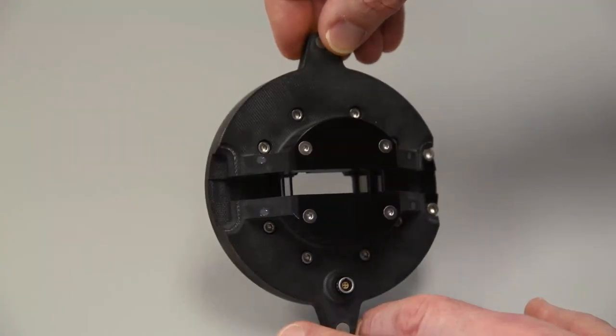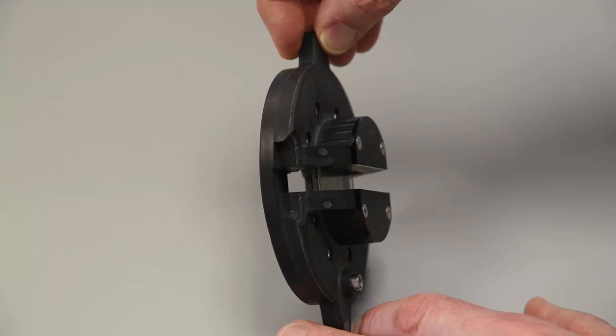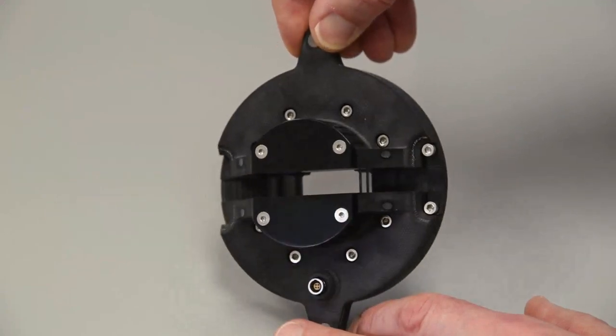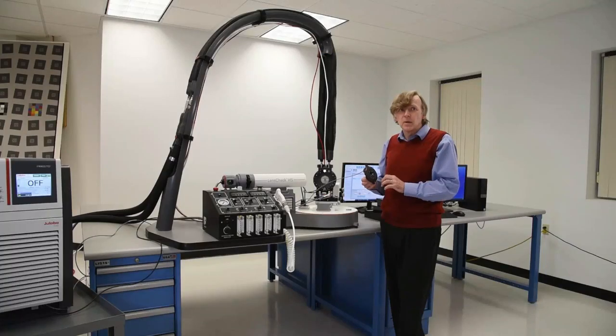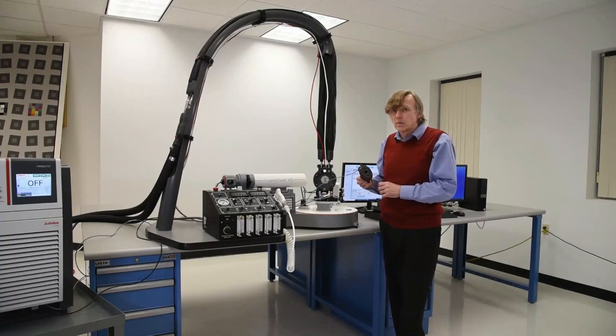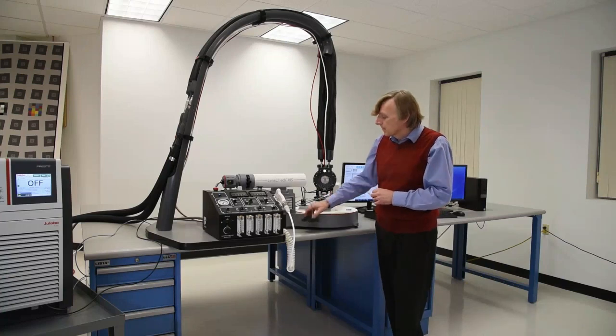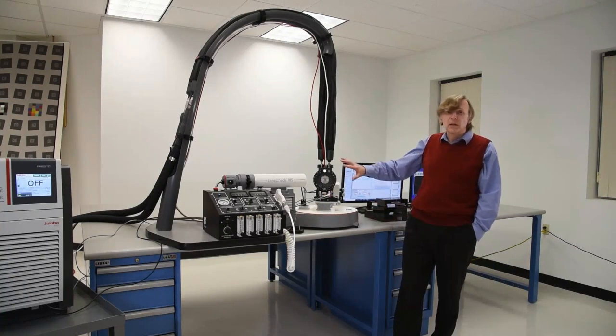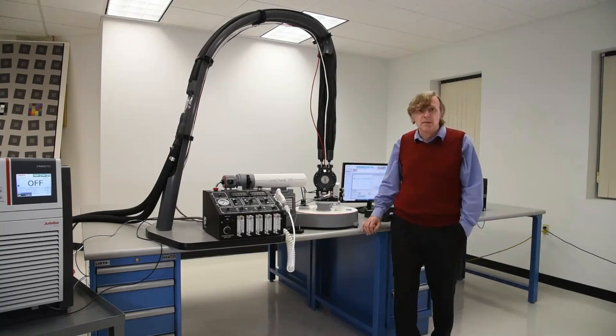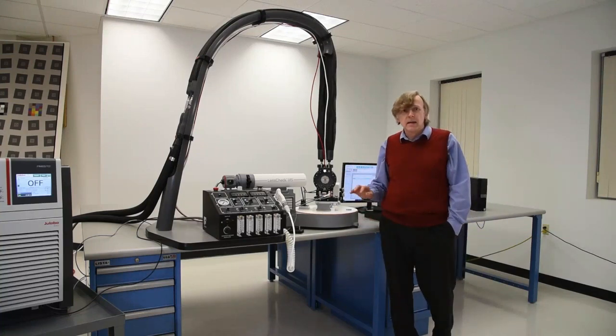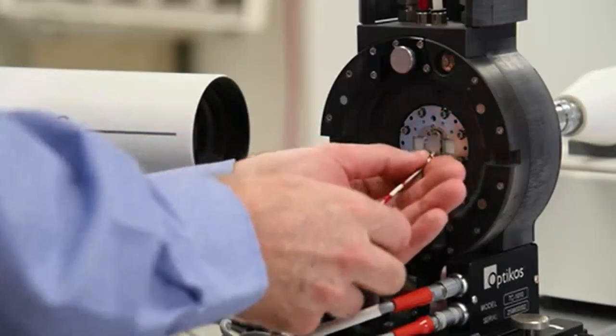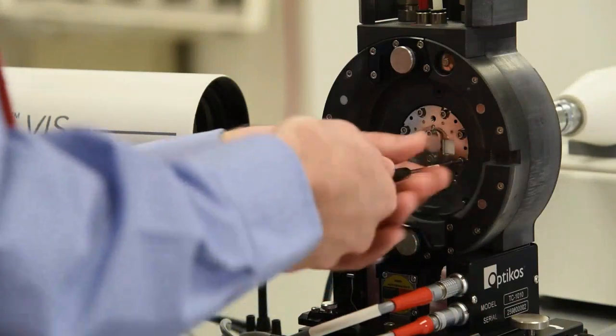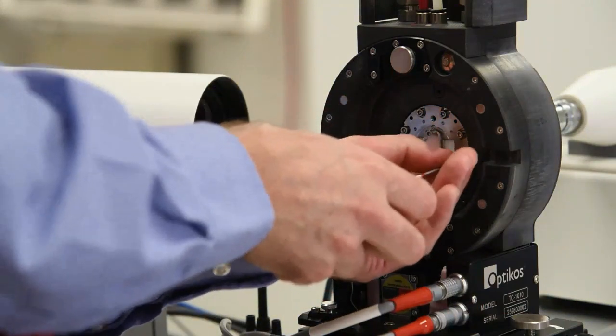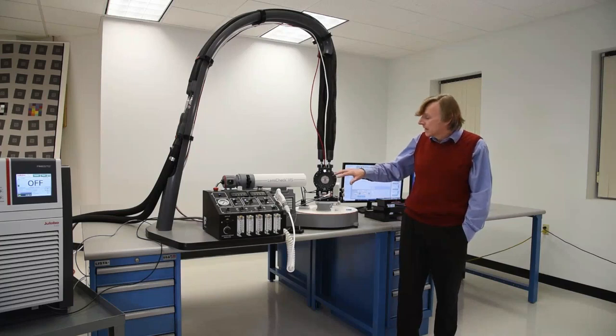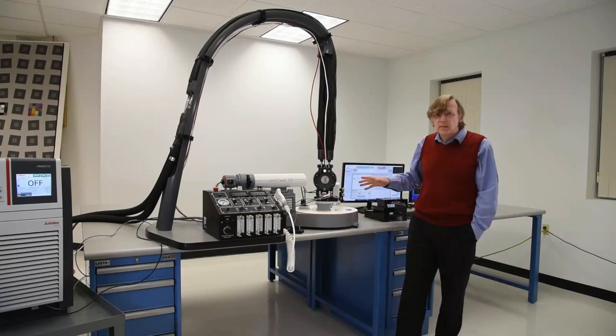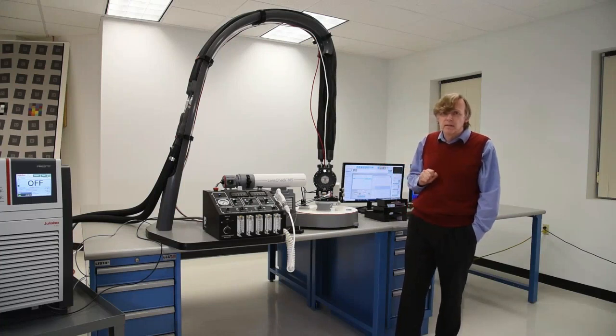The window itself consists of a high-quality double-paned segmented window. This necessarily means that there is a small blind spot on either side of the optical axis where the segments meet, but its effect is relatively small in the case of the wide-field lenses for which this chamber is intended. At last, we have peeled back the layers of the onion and have arrived at the lens itself, and it is time to address the question of how the lens is mounted to the heat exchanger. As you may have expected, this requires fabricating an interface plate specifically for the lens to be tested. Only by doing so can we ensure a good thermal contact from the lens to the heat exchanger. Customers typically design and make their own interface plates, but Optikos can certainly do this for them.